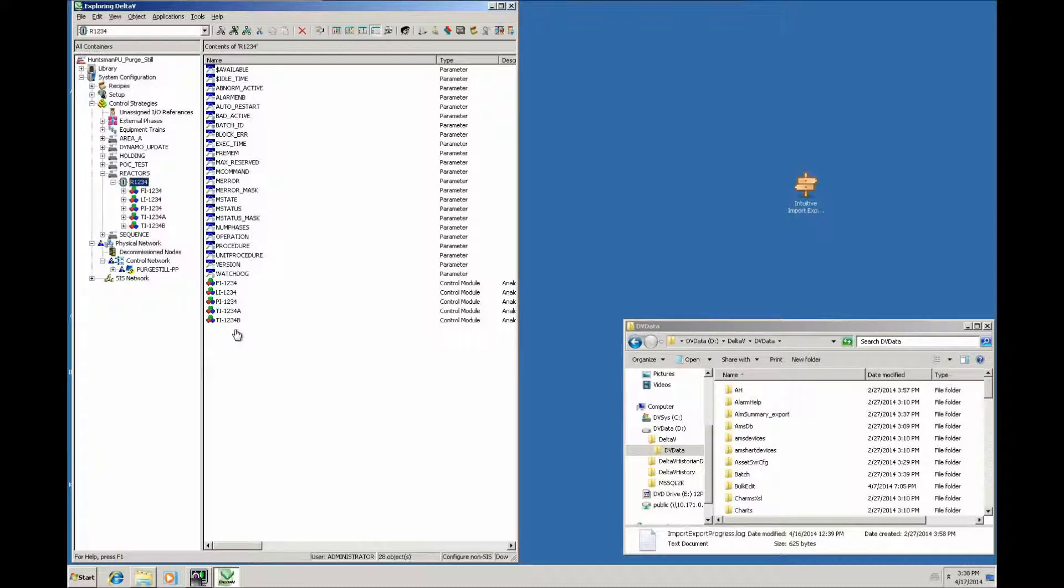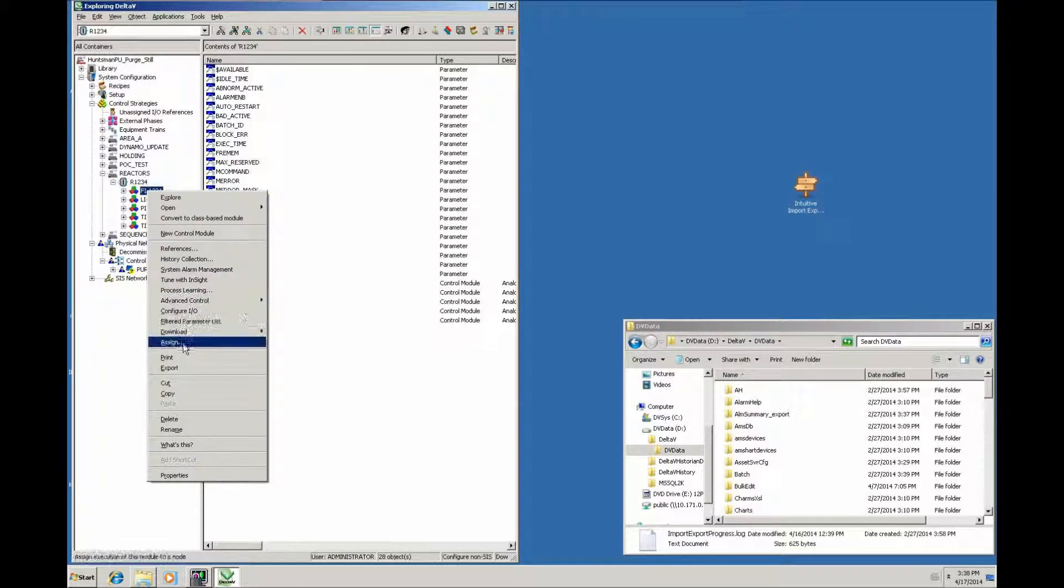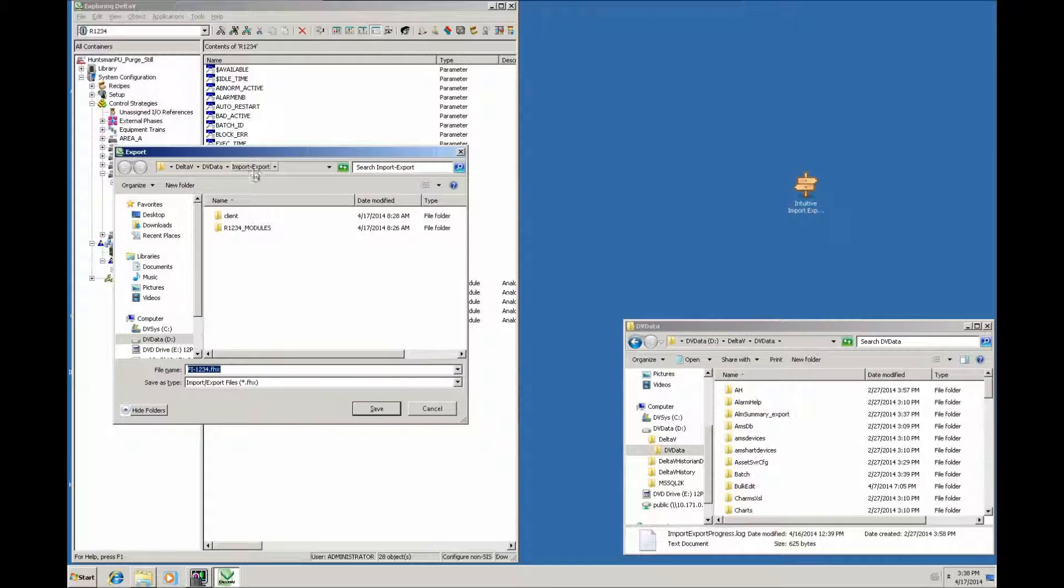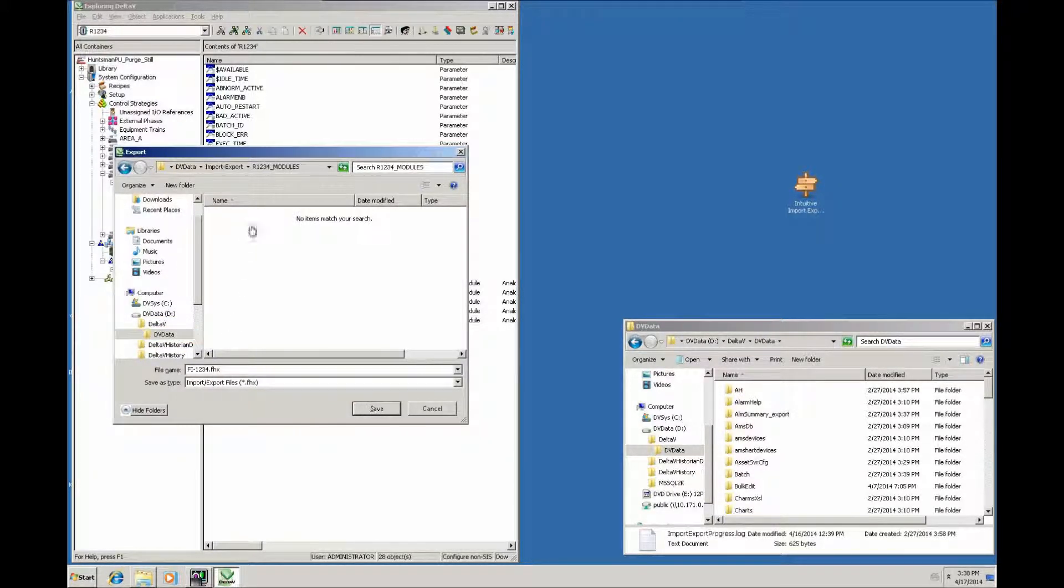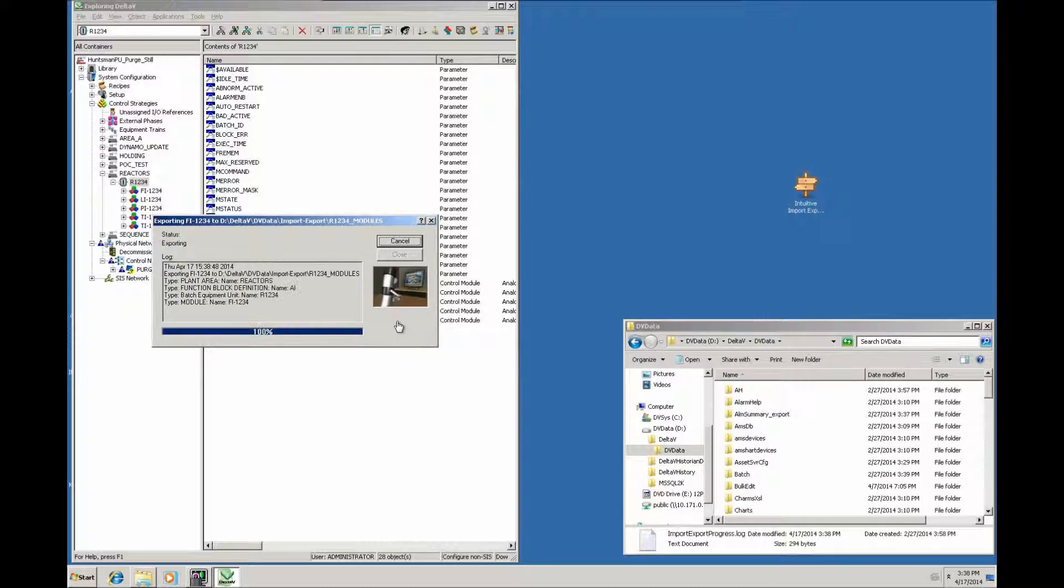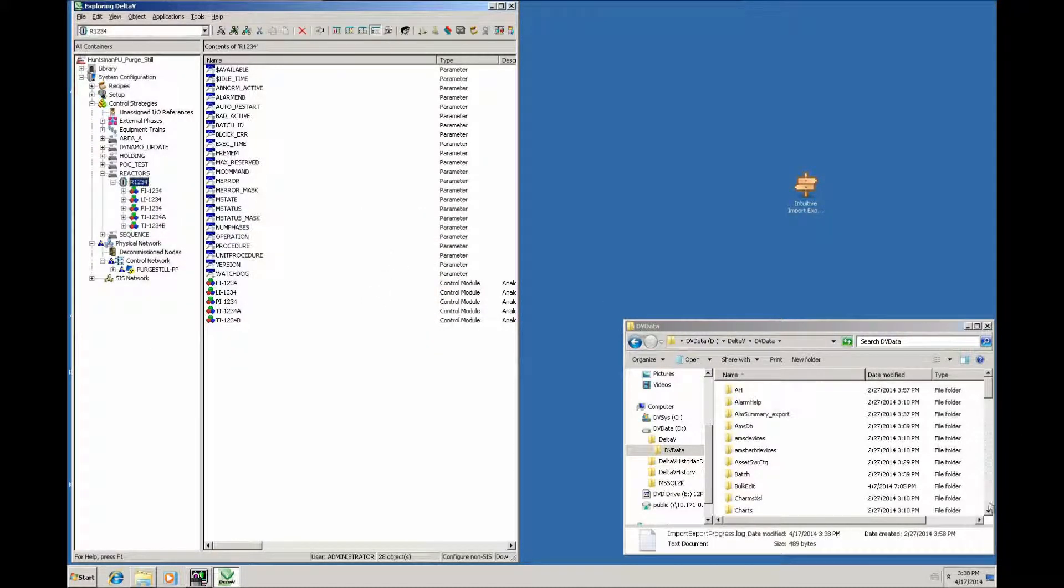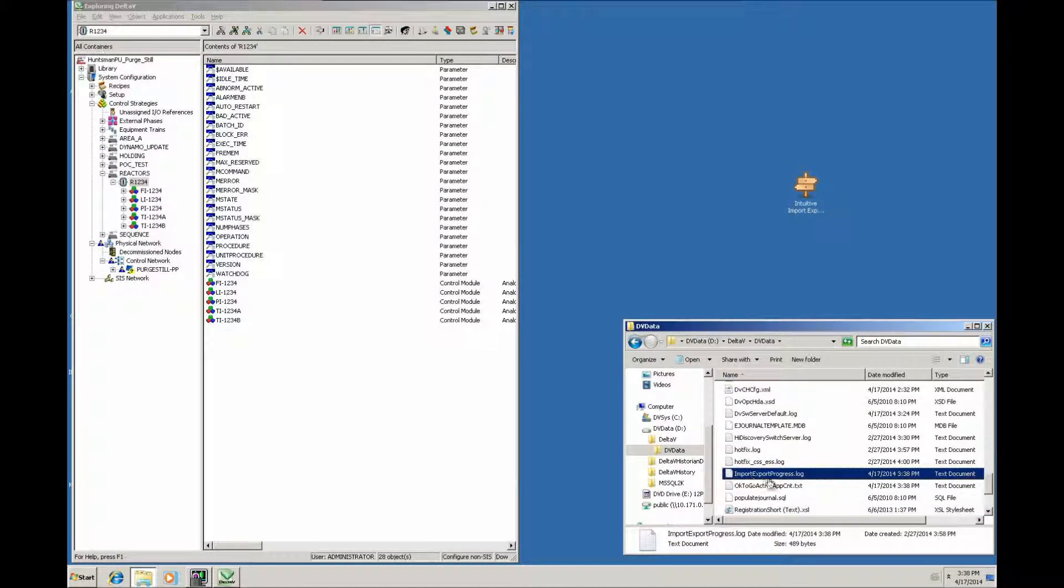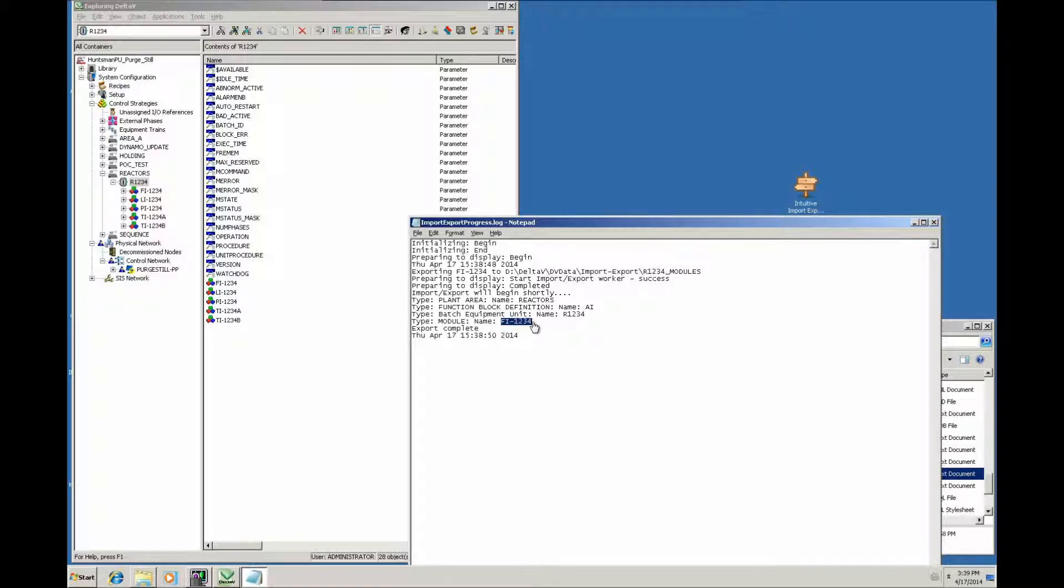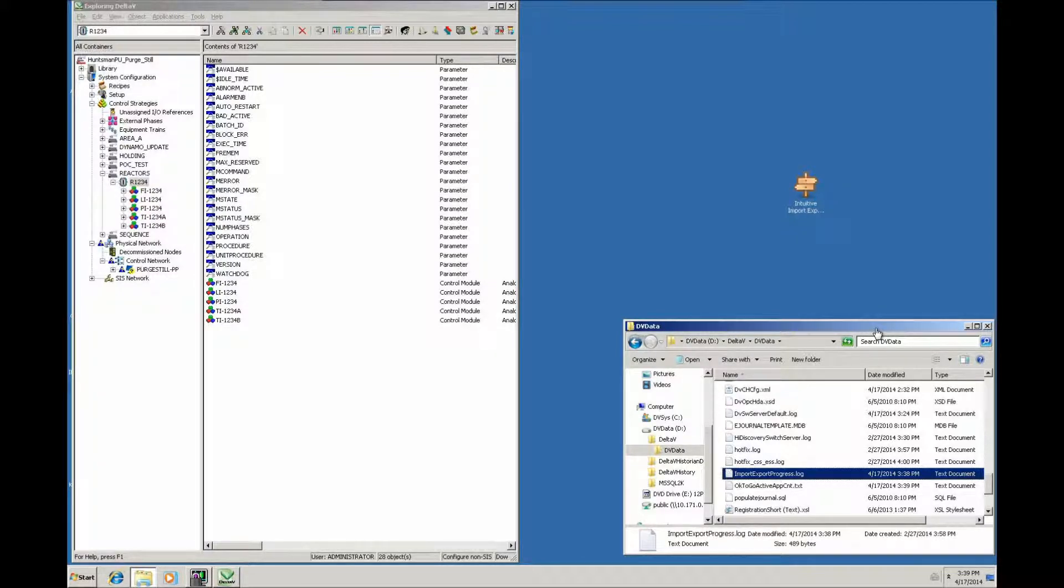They're going to export each of these items individually and then send it to the main office for import. When you do an export, it typically automatically goes to the import export folder in the working directory of Delta V. Now he's going to export them into a folder called R1234 modules. What you'll see is that's actually created or updated a file called import export progress log which lives in the DVData root folder. If we look into that, it actually shows what was in the export.